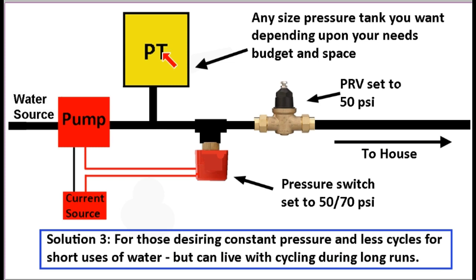So what happens when you have this big pressure tank is that it fills up, let's say, to 70 pounds, and then the pump goes off, and the pump will not go back on until the pressure tank goes back down to 50 psi, and then the pump will go on because this pressure switch is set to 50-70. So if you have a large pressure tank here, you can get a lot of short runs. You can get a lot of washing your hands, washing a dish, flushing a toilet. You can do that quite a number of times before the pump will go back on.